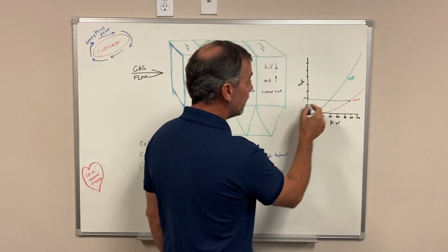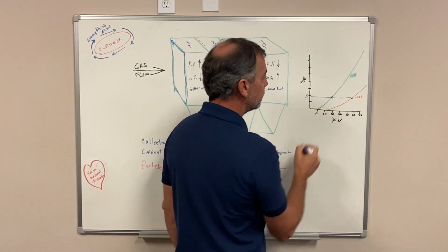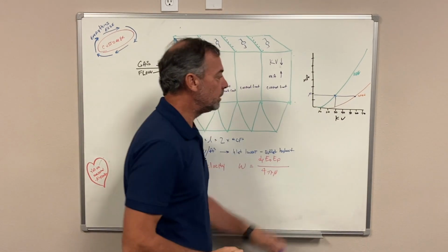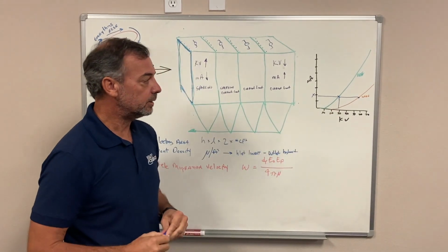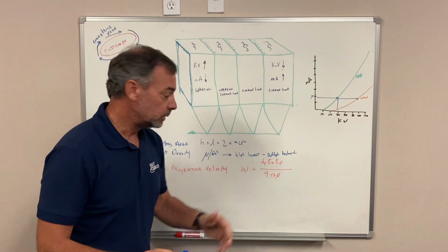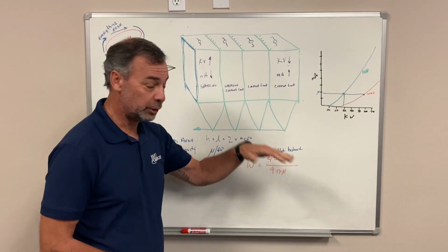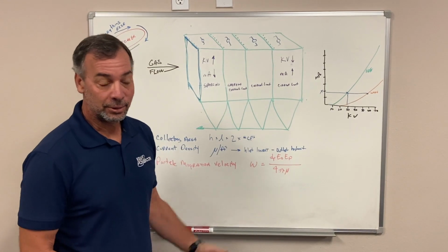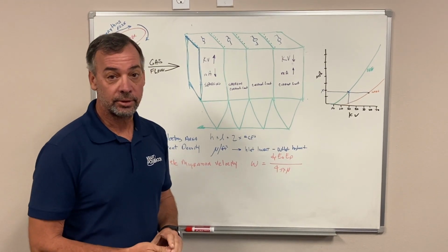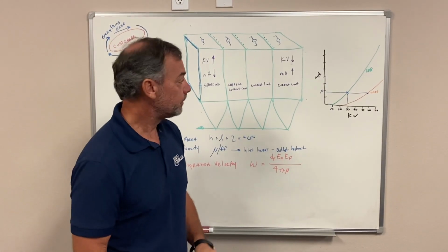Now, if that's your TR set limit, this is your limit for voltage. So you're limiting your voltage only down to 30 kV. Same current, but if you go down here, voltage is in here twice. So if you reduce voltage, your particulate collection efficiency goes way down real quick.